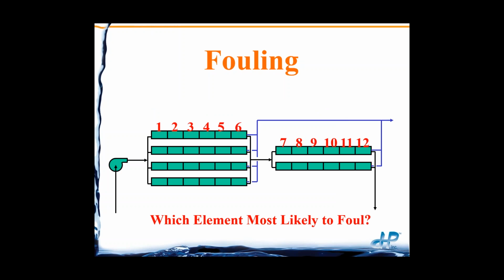So when we're talking about fouling, which element is the highest fouling? All right, so if you said number 1, then you are correct. And again, that's mainly because of GFD. So when you have a problem in the first stage, the chances are we're talking about fouling. If we have the problem mainly or only in the second stage, then the first thing we'll think of is scaling. It's not always, but more times than not.